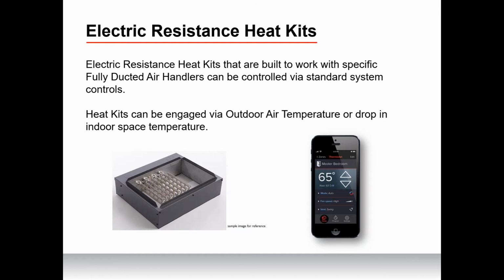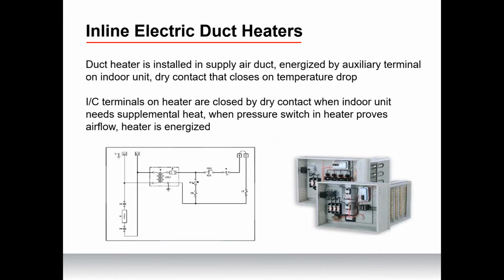So if you're sized appropriately and the load's low enough, you don't really need supplemental heat. But if you're putting in the air handler, put a heat kit in. It's simple enough to do. I would 100% do it in my home if I was putting in that application. It just makes sense to do it because it's so easy to integrate. So if you're dealing with a fully ducted air handler, the electric heat kit is really, really simple to control. Absolutely easy to do, be it outdoor air temperature or a drop in space temp. It's very, very simple to do.